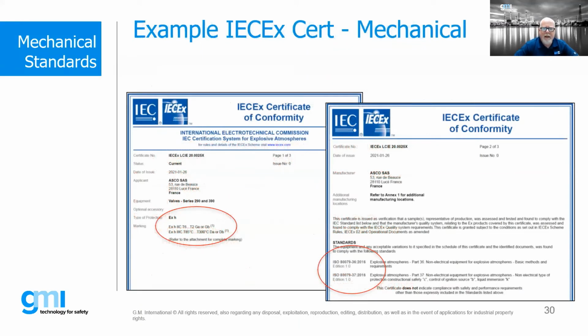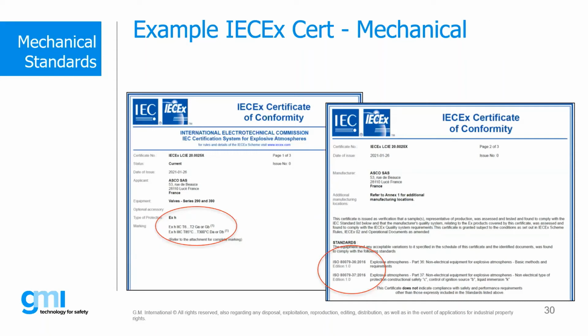So looking at a certificate - this is a certificate of conformity, an IECEx certificate of conformity. Notice that this particular product is a valve. This is not traditionally an electrical product, but it's marked EXH, and we have a similar marking string to what we'd find on our electrical equipment. Notice that the standards applied here are ISO 80079-36 and 37. So we're now seeing many customers and clients starting to make it a requirement that mechanical equipment also be certified in some way, shape, or form.